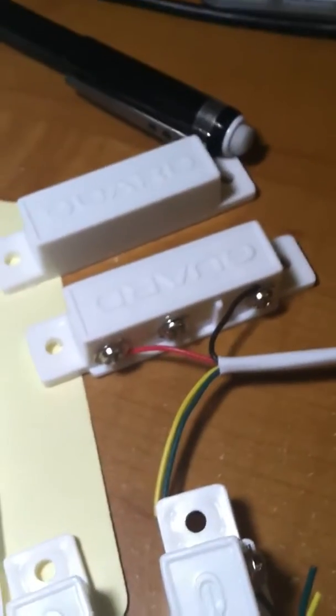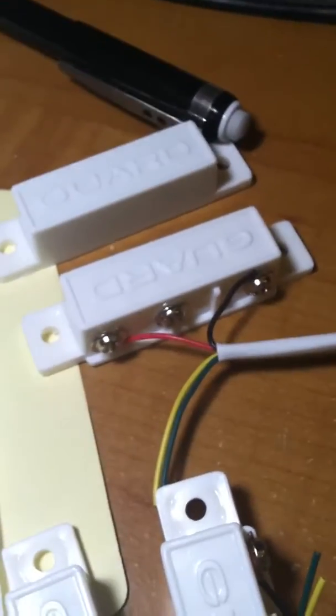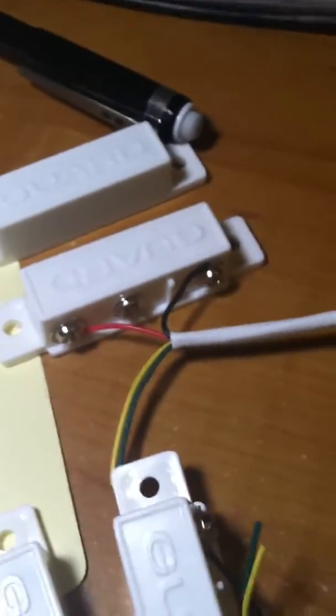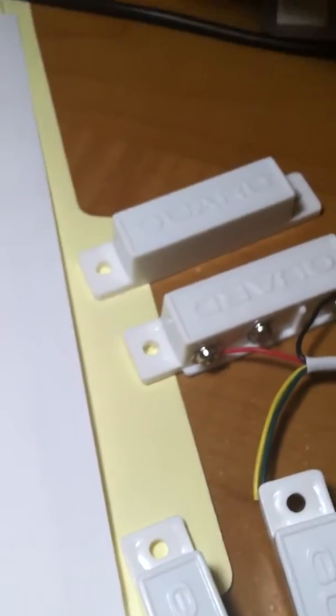It was chosen to make the door switches normally closed, so that for some reason a wire was cut, it would trigger a door opening event. Instead of, if you used a normally open setup, cutting a wire would not trigger any event, and it wouldn't even be known that a wire was cut.